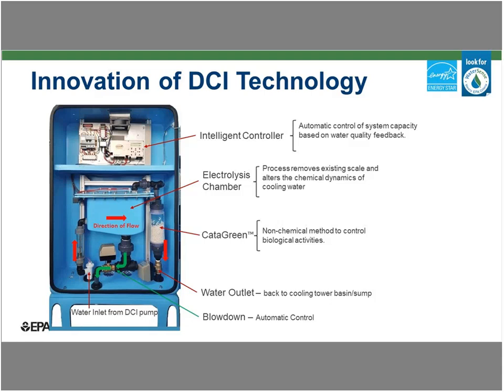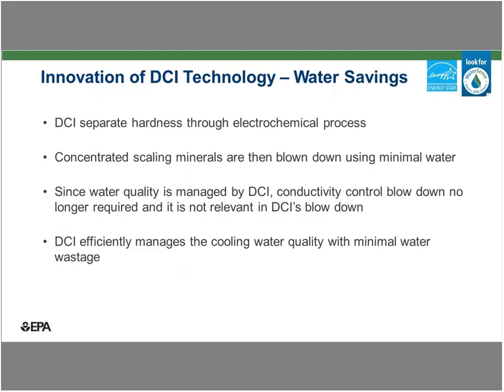Our blowdown water, of course, you can use for other purposes, like watering plants and other things, because there's no chemical in there. So DCI separates hardness through an electrochemical process. The concentrated scaling minerals are then blown down using minimal water. During our regeneration process, we use very minimal water to flush out the scales. Since water quality is managed by DCI, conductivity-controlled blowdown is no longer required.